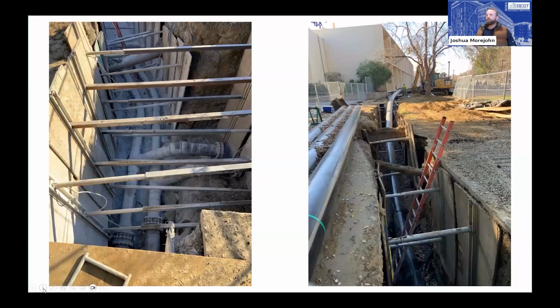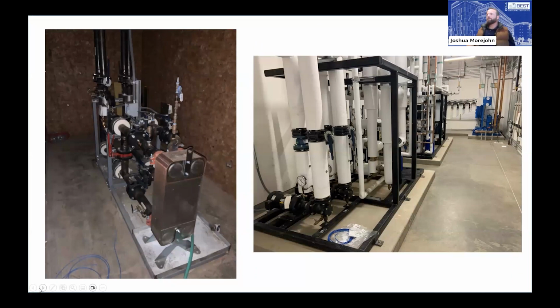Now looking internal to the buildings — what's surprising is how much smaller your heat exchanger skid is if you have one for the hot water side. We had the good fortune of all of our buildings, for the most part, already having hydronic hot water systems inside. So we're just tying into the mechanical rooms, not getting into the building systems themselves, and supplying the existing hot water systems with a new heat source. Instead of having steam to heat them, they now have this low temperature hot water.